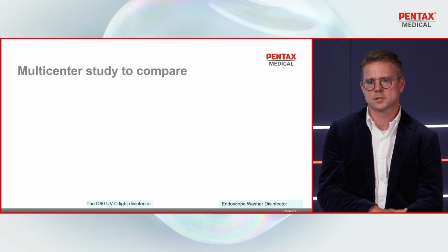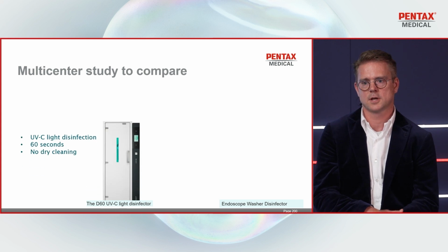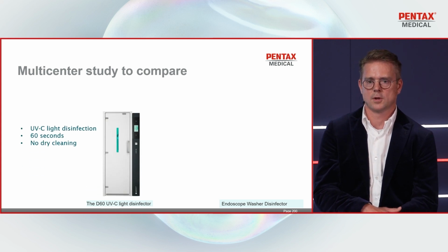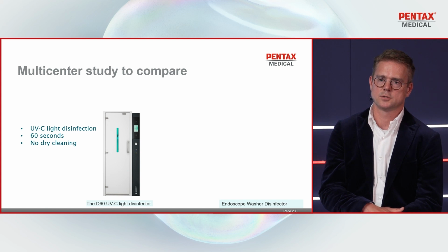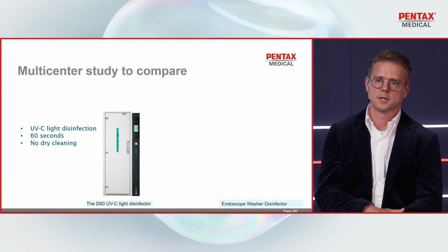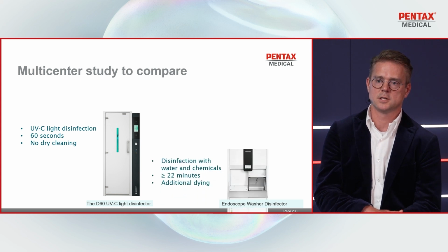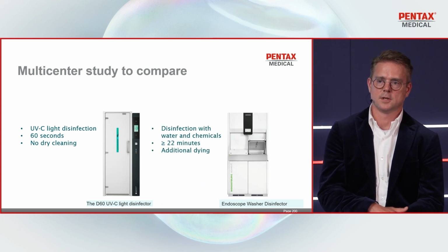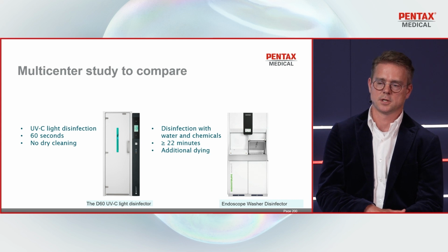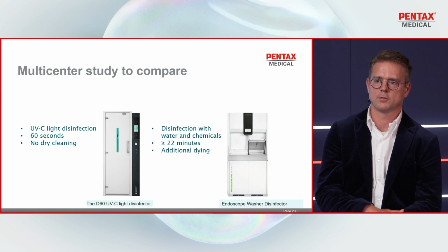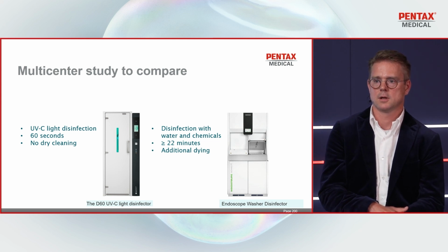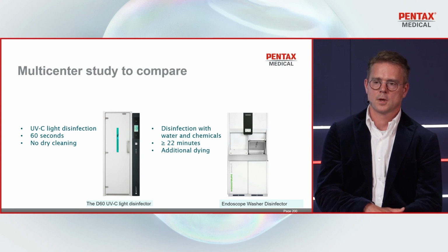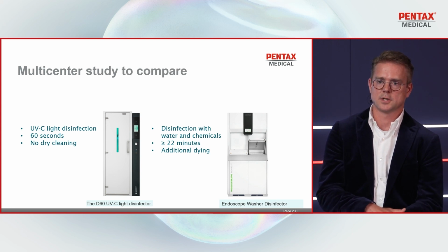That's why first we did a single center study in our own hospital, and after that we did a multi-center study to compare the UVC light disinfection machine, which has a process of 60 seconds and no dry cleaning is needed. And we compared it with the washing disinfector, which uses water and chemicals and takes normally about 40 minutes to clean the endoscope. And of course, additional drying is also needed.